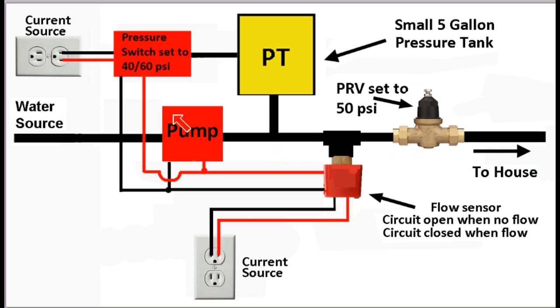through the system. And what happens, even if the pressure switch is showing, it has the pump off, the water that's stored in the pressure tank will cause there to be a flow that goes through here. And as soon as this flow sensor detects a flow, the flow sensor will turn on the pump, and the pump will pump water at this pressure reducing valve, which is set to 50 psi. And since the water is continually being used, the flow sensor is continually being on, and the pump will stay on, and you'll get a constant pressure of 50 psi.